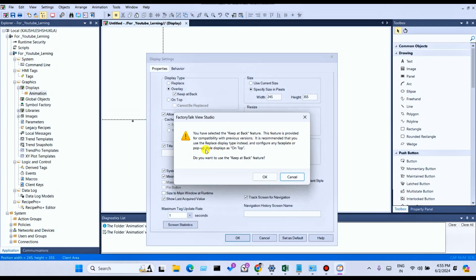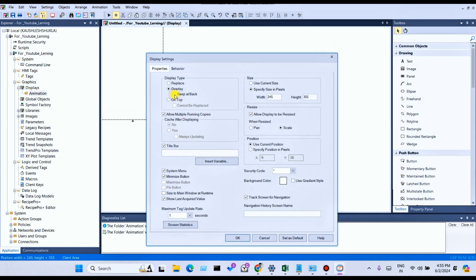It is recommended that you use the Replace display type instead. Configure faceplate or pop-up style display, or On Top. If you want to use the Keep at Back feature you can select OK. But in my experience, most of the case I have not selected it. I have never selected Overlay in any project. Always select Replace for display and On Top for pop-up. On Top cannot be replaced. So select Replace here.